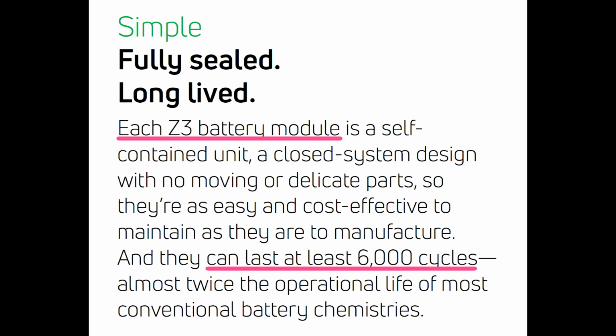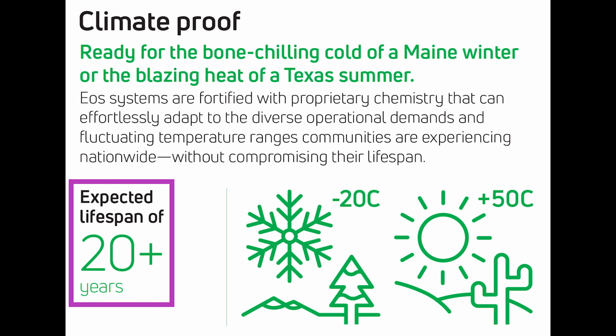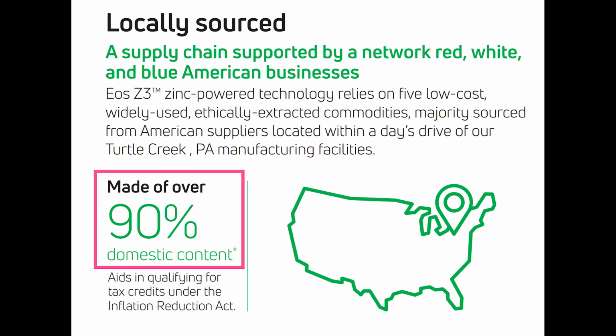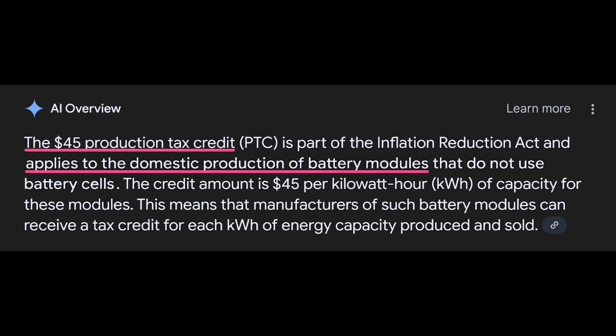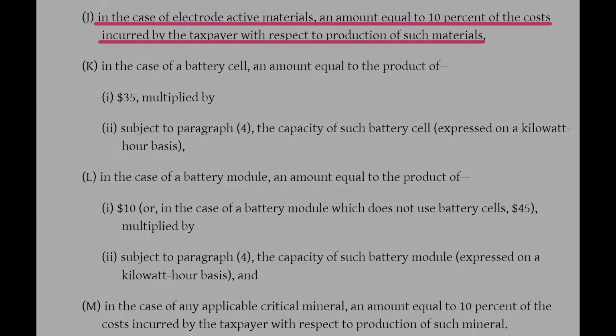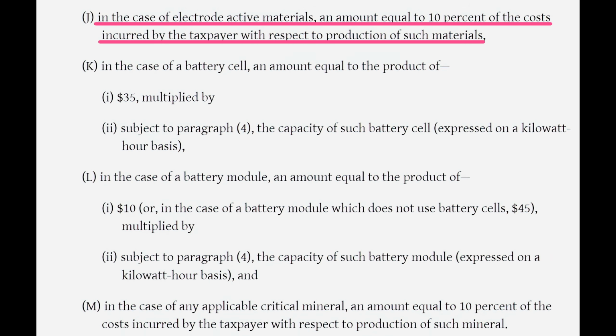Fourth, zinc bromide batteries are very durable, offering at minimum about 6,000 charge-discharge cycles at 100% of their capacity and lasting for 20 years with minimal degradation. Fifth, over 90% of the EOS supply chain is within the US, and they aim to eventually get that to 100%. That provides EOS with supply chain stability and also gives them access to production tax credits of up to $45 per kilowatt hour, and possibly up to $52 per kilowatt hour if the 10% active material tax credits are included.